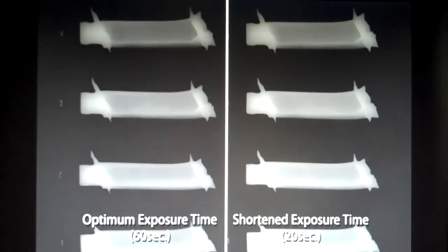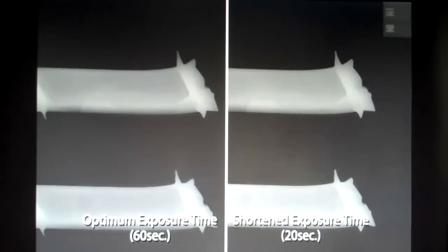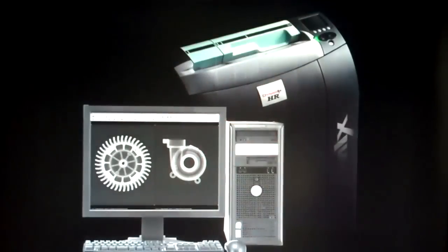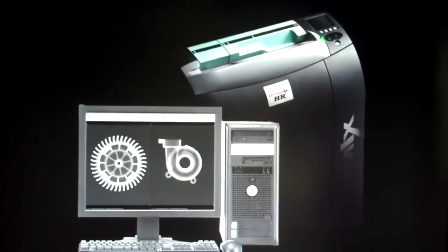Because of the high sensitivity of the imaging plate, quality images can be obtained at 1/10 to 1/2 the radiation dosage of conventional films. And depending on the purpose, the amount of radiation dosage can be reduced even further, although the image may not be as sharp. The combination of Fujifilm's EDR technology and imaging plate technology has enabled the easy and speedy output of high-resolution images, making full use of the imaging plate's high sensitivity and wide dynamic range characteristics.